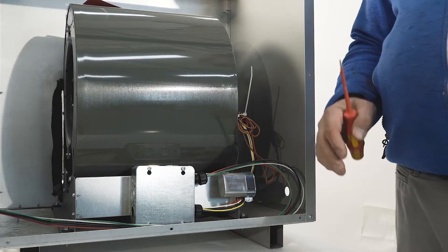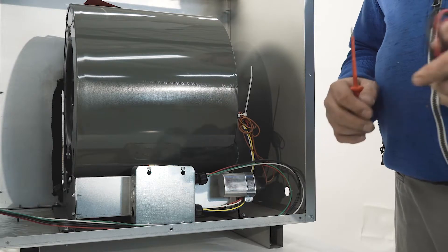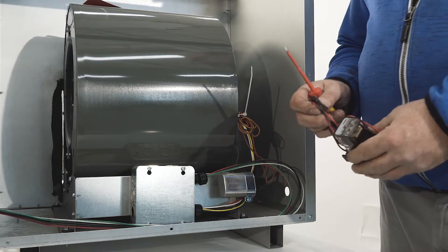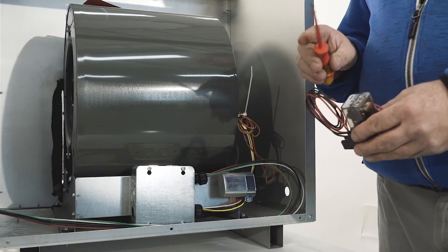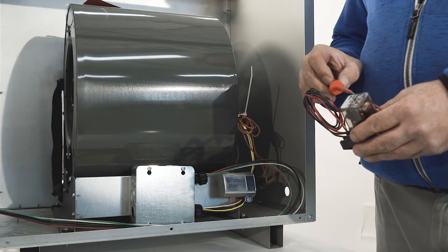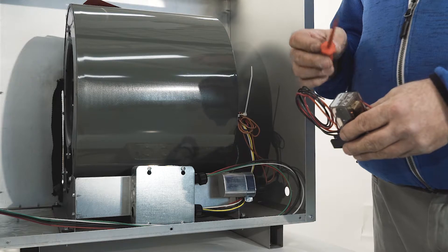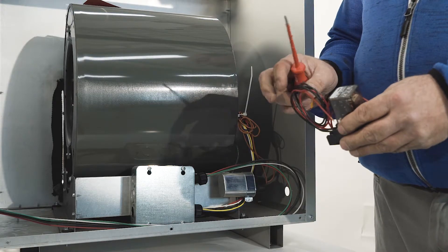To get started wiring our air conditioning to an HMF 150 or 200 wood burning furnace, you definitely need to get the HMF-K AC2 relay. What this relay does is it takes the 24 volt circuit switch for air conditioning for the fan to come on for all three levels and individualizes them to the blower module.